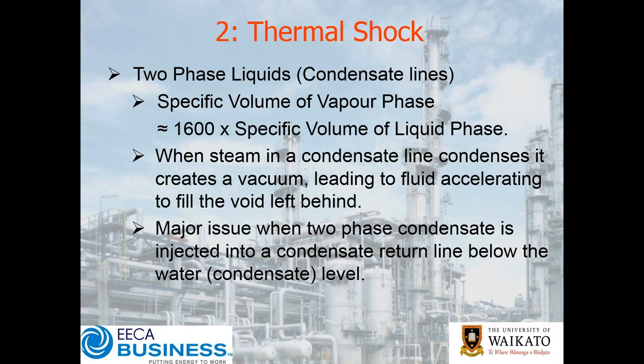Another way of looking at it: one millilitre of condensate explodes into 1.6 litres. If you're in a confined space across the seat of a valve, or in the back end of a steam trap with a couple of millimetre orifice, and you've got a drop of condensate where you don't want it, the drop in pressure that flashes off that little drop of condensate becomes a very big volume very, very quickly. It's an uncontrolled expansion of a gas — and isn't that not the definition of an explosion?